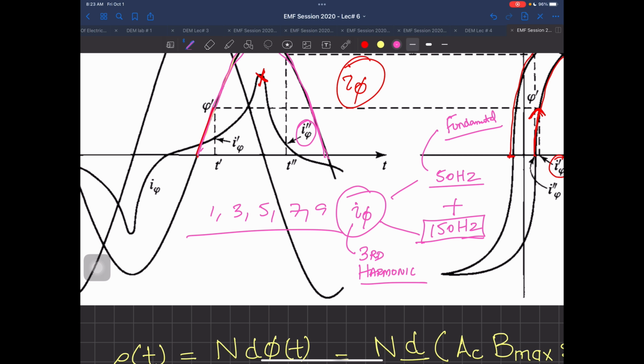I'm repeating: your I phi here has a non-sinusoidal shape, as you can see with the bulge. This bulge is created because two waveforms are added together - one the fundamental 50 hertz, the other the 150 hertz waveform - and this happens because of saturation of the core.